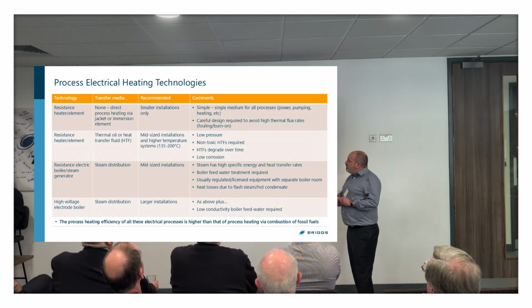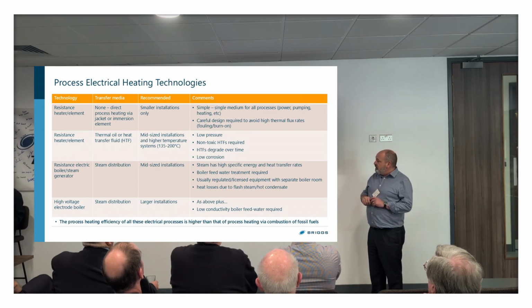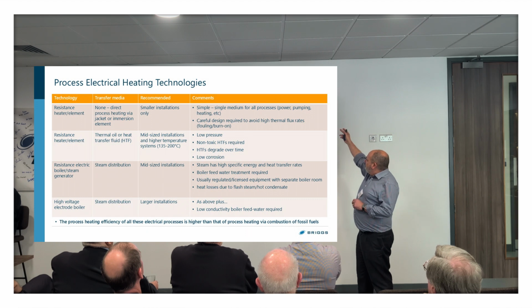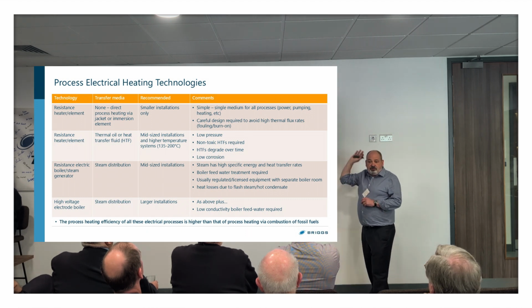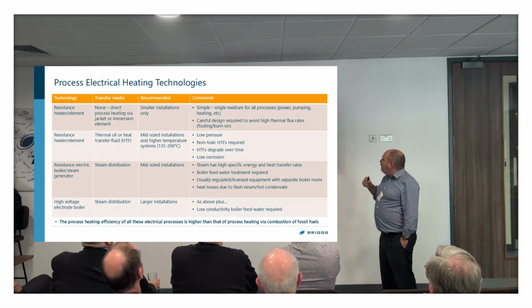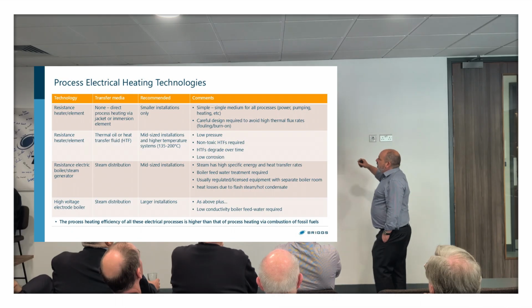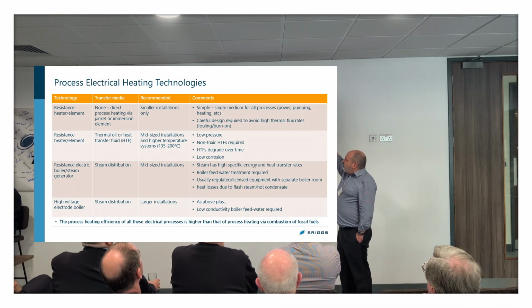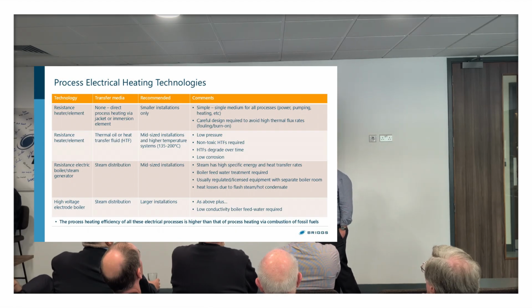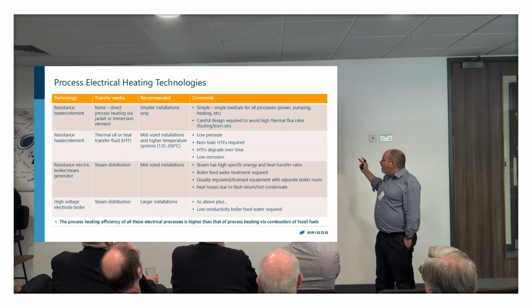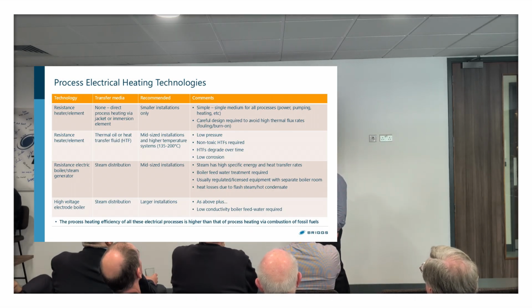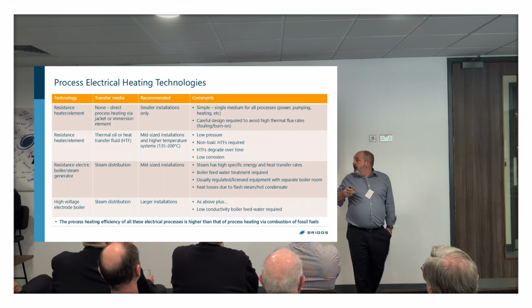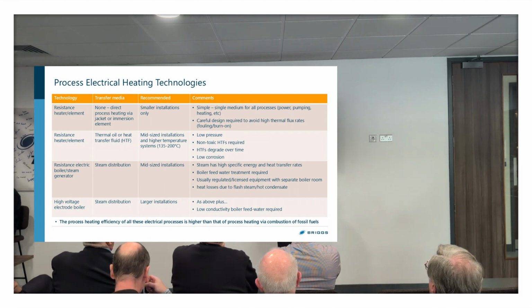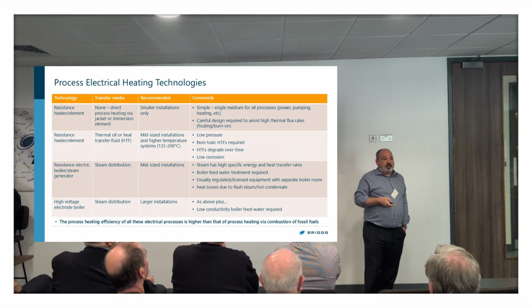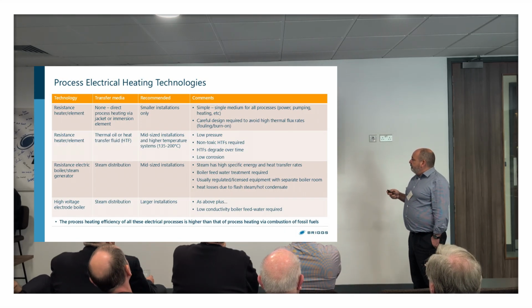So how do we use that electricity in the process for heating? Very simple. First row, people have been doing that for years. Electric heating elements, kettles, etc. You can do that on an industrial scale. Known technology. A few installations we've done use a thermal oil heater to move heat around the plant. But on a larger industrial scale, we wanted to use the advantages of the steam distribution, which our customers usually already have, and change over their boiler to either a resistance or a high voltage electrode boiler.